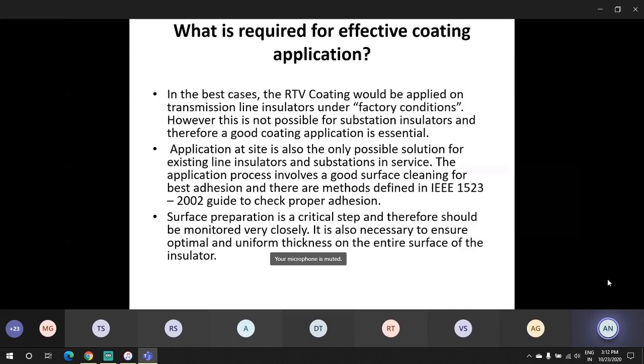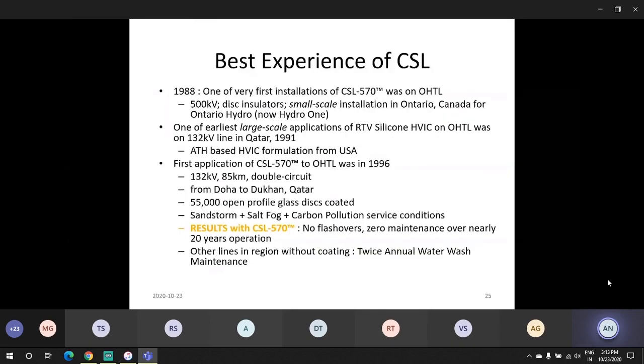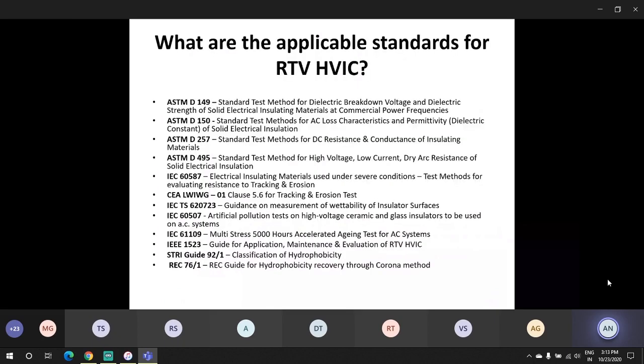The effective coating application has to be in accordance with the application manual or the guidance issued by the manufacturer and the methods defined in IEEE 1523. In our case, the best experience of CSL, our oldest application was done in 1996, on a 132 kV, 85 kilometer double circuit line. This is still in service even after more than 20 years.